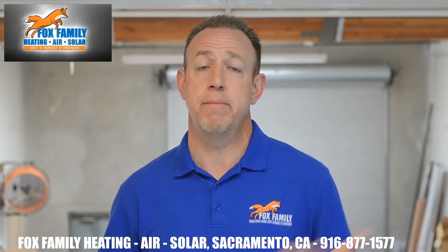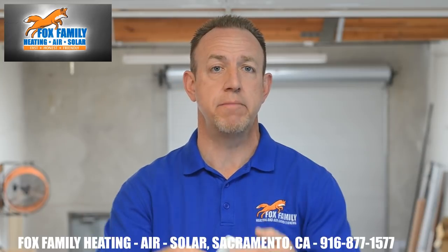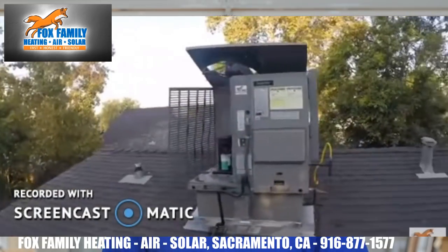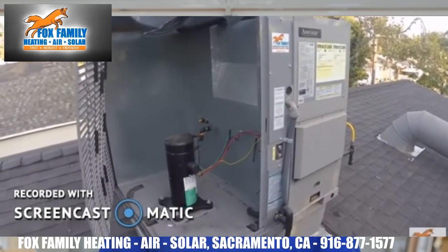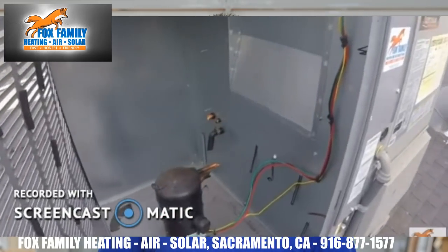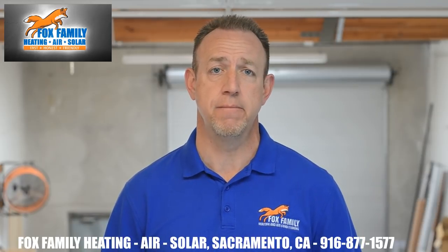You might say, well, my AC is a package unit up on the roof. These units are still required to have locking caps on them unless you have some sort of locked area enclosing the system to prevent tampering. People can still get on your roof and steal your AC if they really want to. Just a few months after we installed a brand new system on a rooftop in Sacramento, the copper coils were stolen right out of the system. Neighbors reported seeing someone up there, and then a big spray of white coming from the unit — that was refrigerant spraying into the atmosphere when the copper refrigerant lines were cut and removed. But adding locking safety caps will help to prevent access to the system, and that's really all you can do.